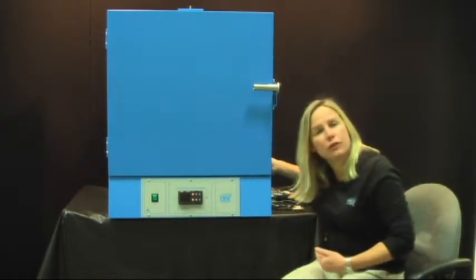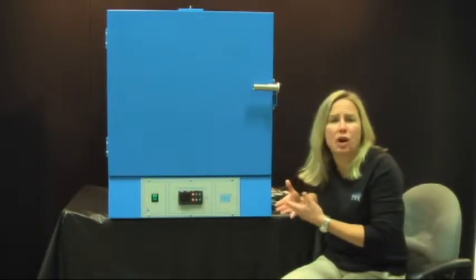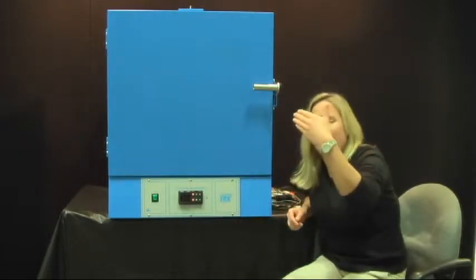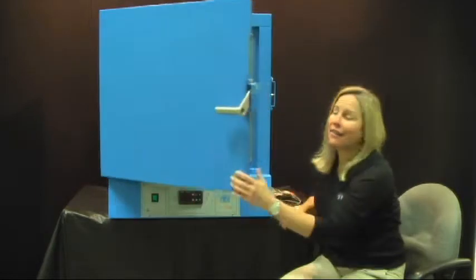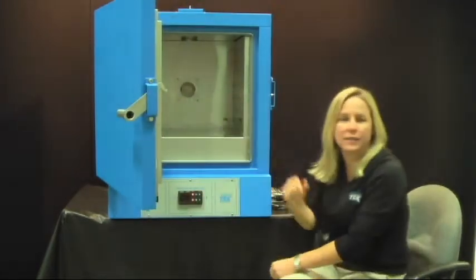The way it works is there are louvers on the side and back of this oven and that's where fresh air is drawn in, passed across heaters, across a fan, and then that air is forced in a horizontal pattern across the shelves.